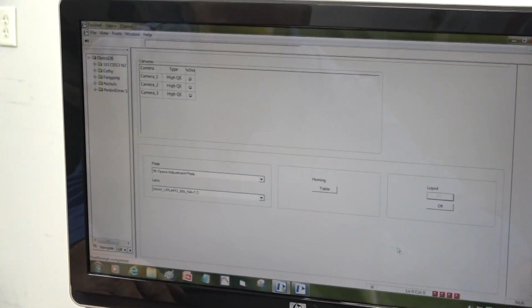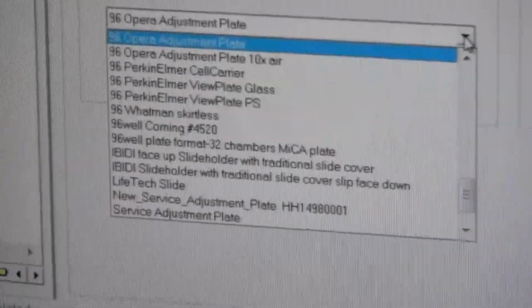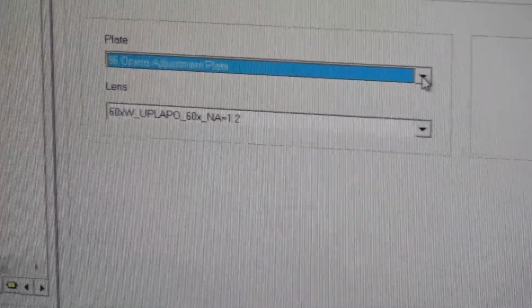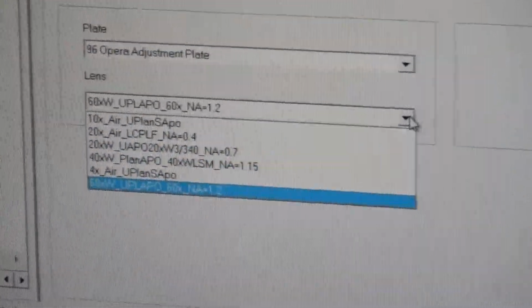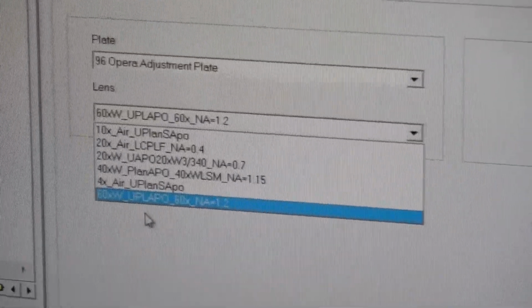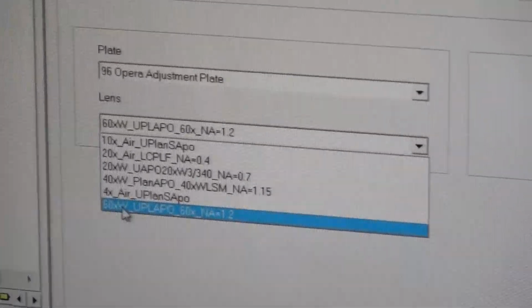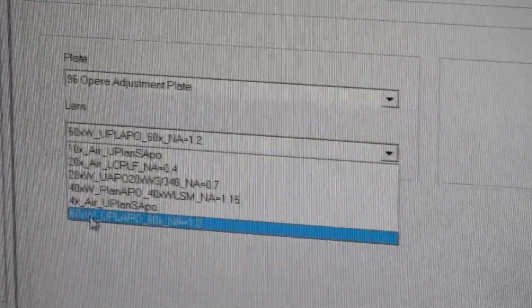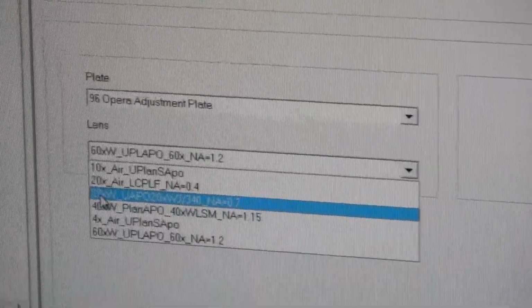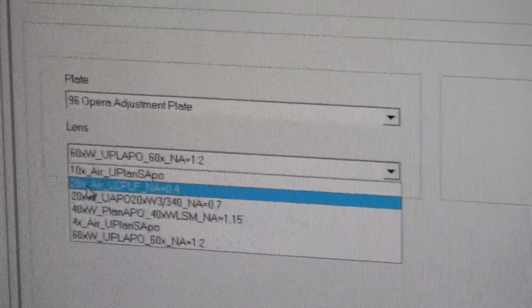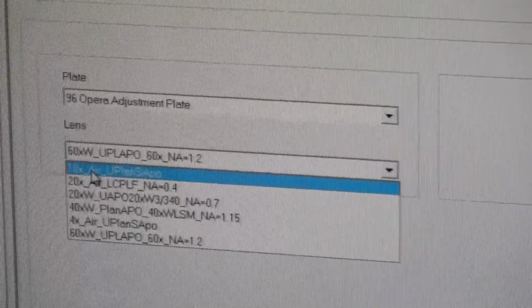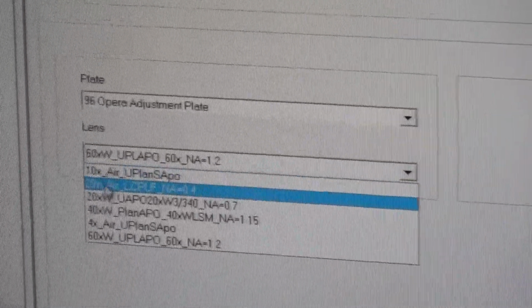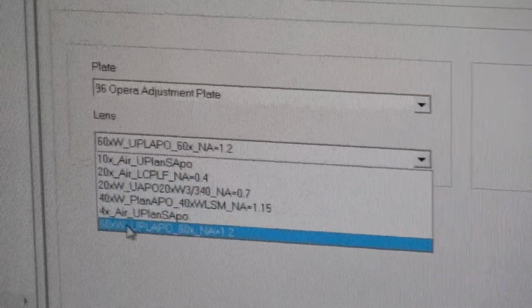And then I'm going to scroll down a little bit further here, and down here you have all the plate options that are already pre-programmed into the machine. That gives you just a myriad of options there, along with some slide adapter plates that you could use. And then down here you have all the objectives. The objectives that are included with this Opera are the 60X water immersion lens, the 40, which is water immersion, the 20, which is water immersion, and 4X air. It does not come with the 10, which you can easily purchase and use, but it does come with 4 objectives. These are your main 4 objectives.